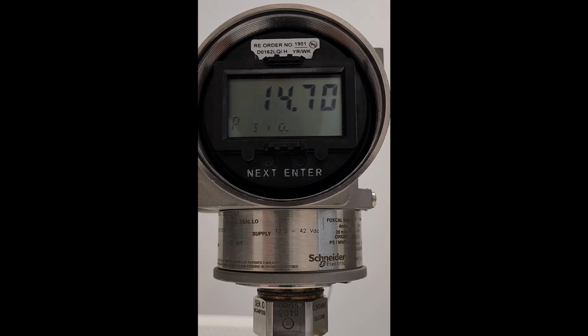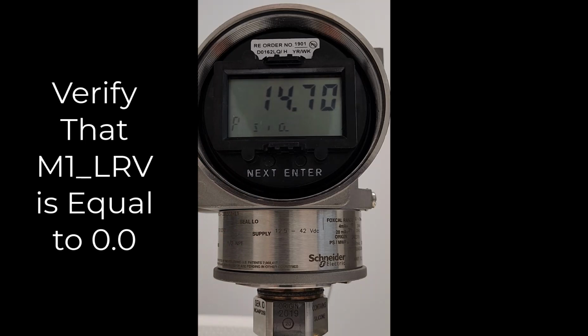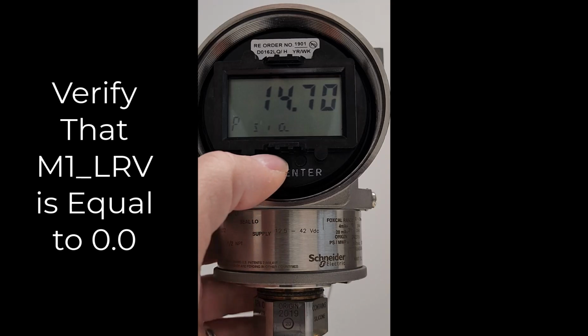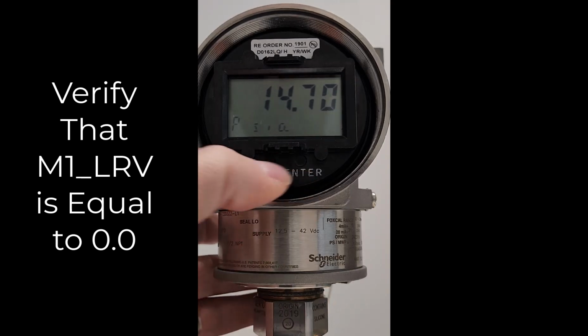Method 2 for having the transmitter indicate 0 when vented to atmosphere would be through the calibration menu. Before we do that, the first thing we need to do is verify that the lower range value is indeed configured to 0, which is very simple.